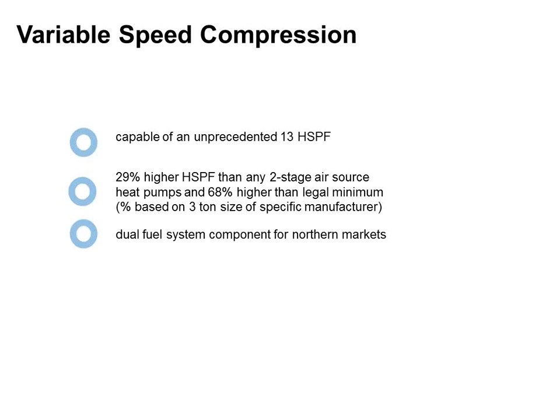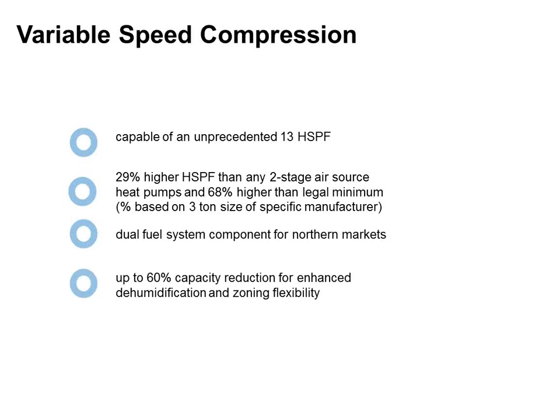The other thing we're going to talk about today is dual fuel systems. You may realize that a heat pump kind of needs to take heat from the outdoor air, and the colder it is, the harder it is to do that. It's not impossible, it's just harder. So there are scenarios where we want to combine gas furnaces with a heat pump, or maybe on a larger system, gas boilers with a heat pump, and kind of get the best of both worlds. So we'll talk about how to do that today.